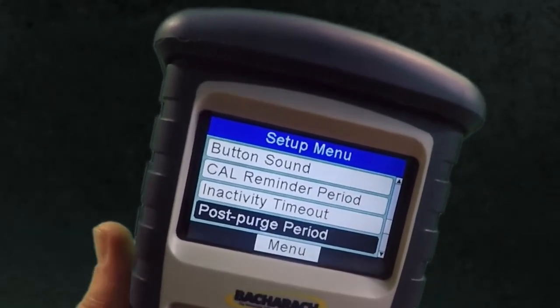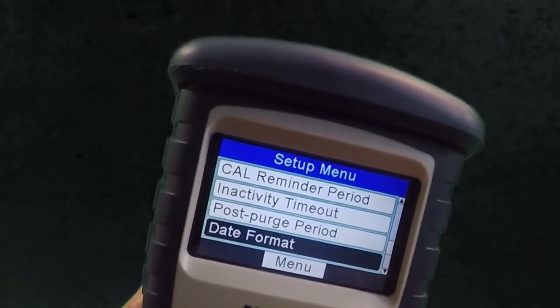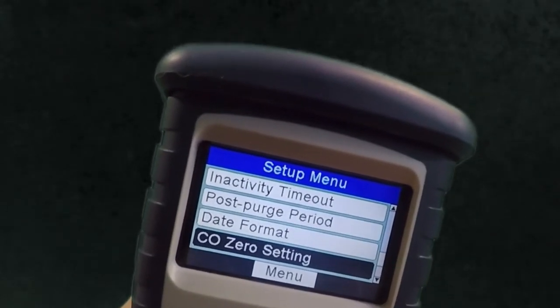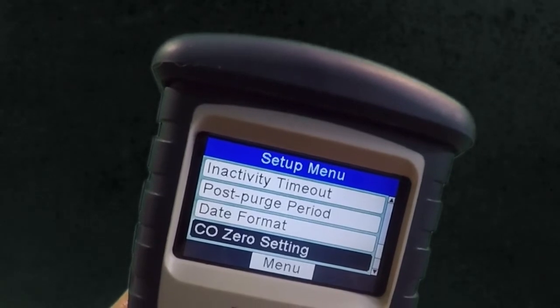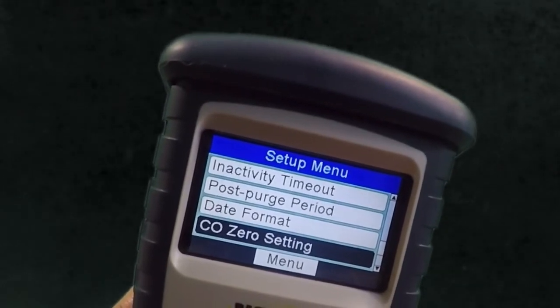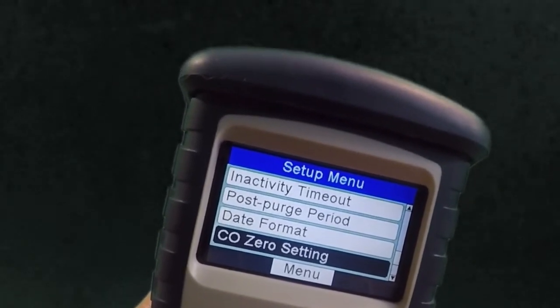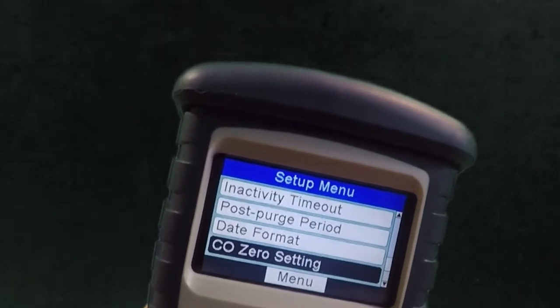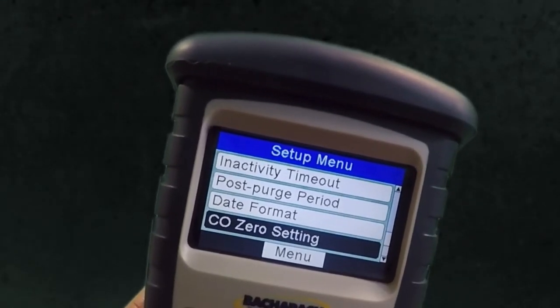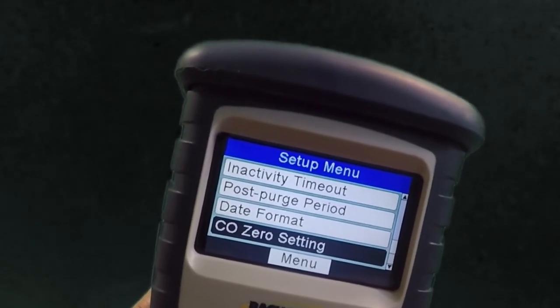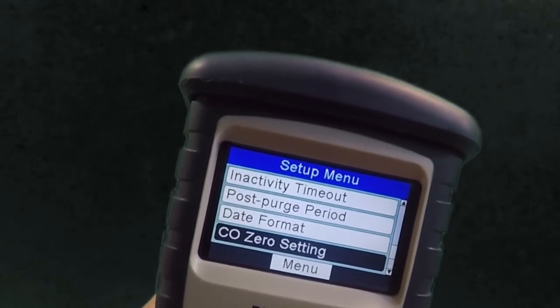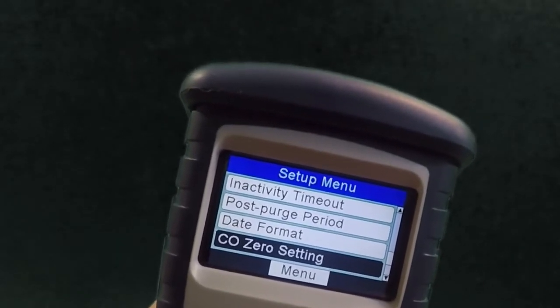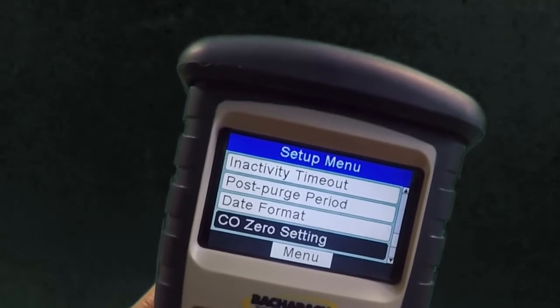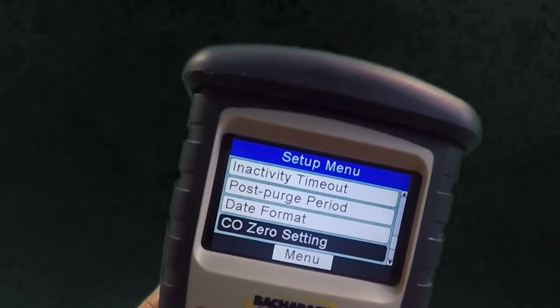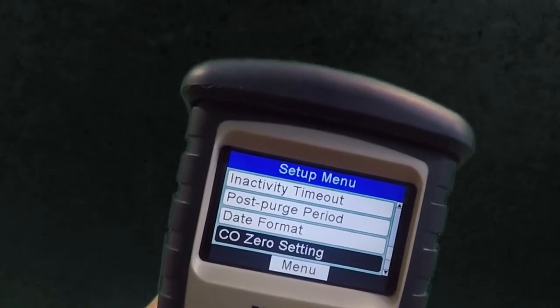The CO Zero setting, as mentioned previously, is a unique feature that Bacharach has put into their instruments, and it's sort of a personal protection device. It helps you, it prevents you from being exposed to too much carbon monoxide without some knowledge that something's going on. Again, Bacharach's the only manufacturer with this feature, so a bit of an explanation is in order.